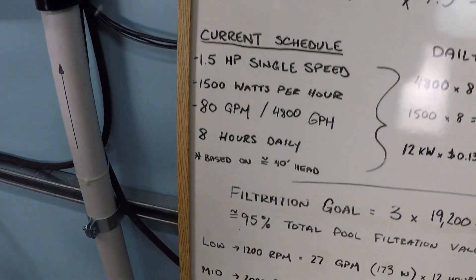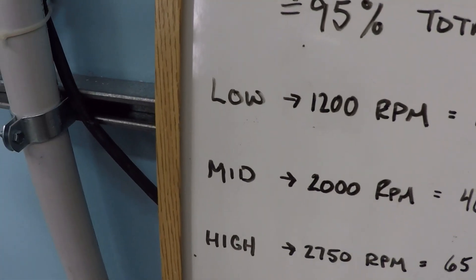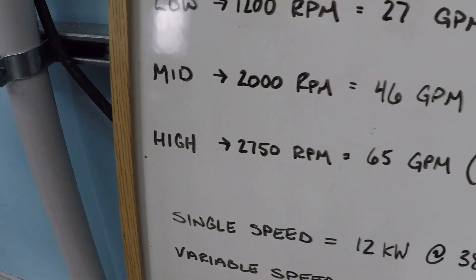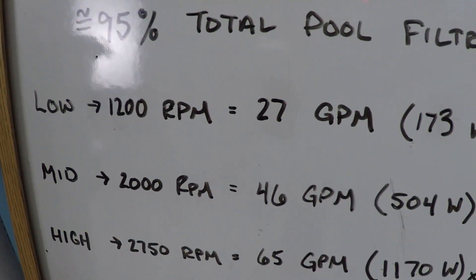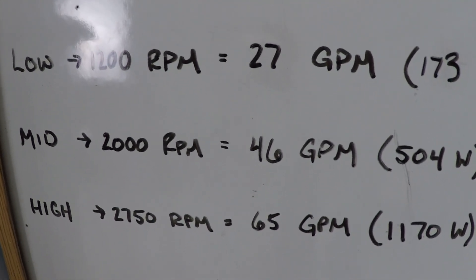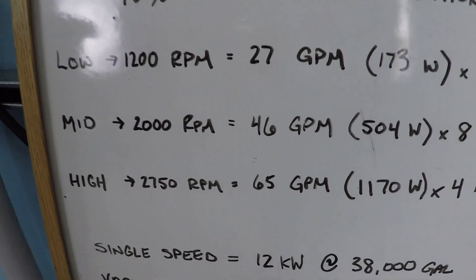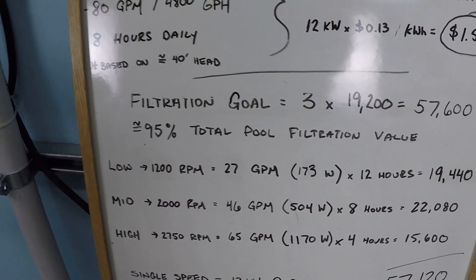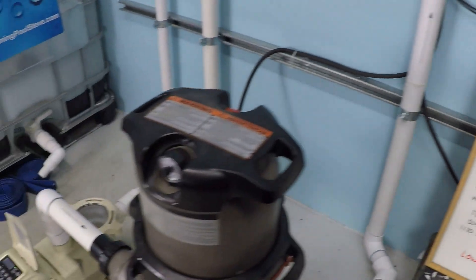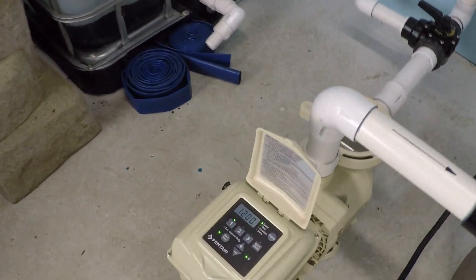In terms of this pump, what we're able to experience with low, medium, and high speed RPM is 27 gallons per minute, 46 gallons per minute, and 65 gallons per minute. It's important that you see that these are real world numbers. So let's take a look at the system running now.